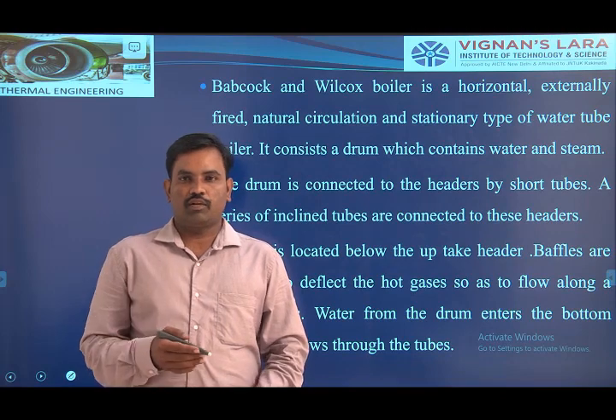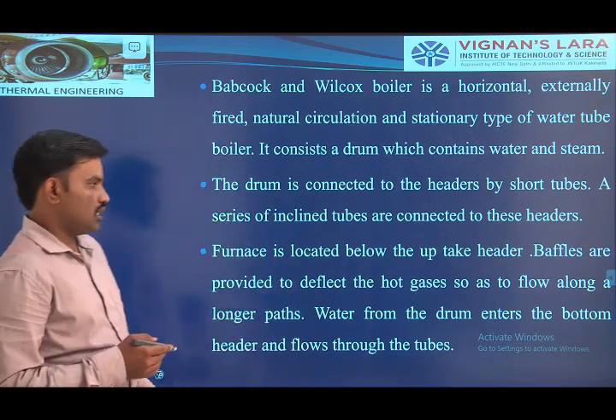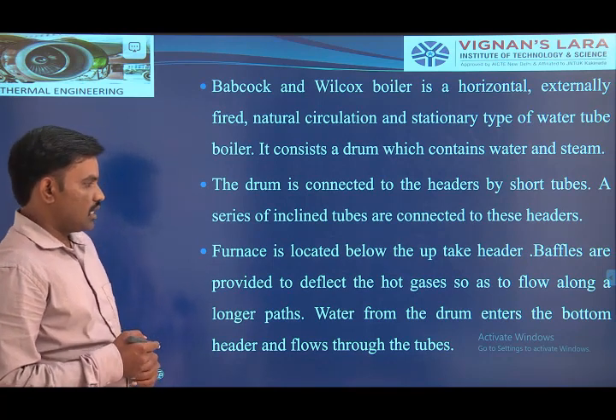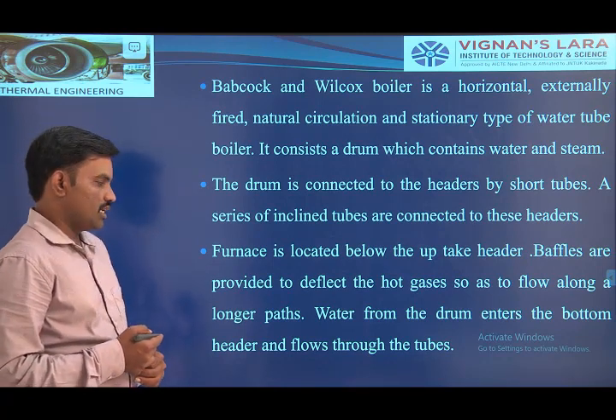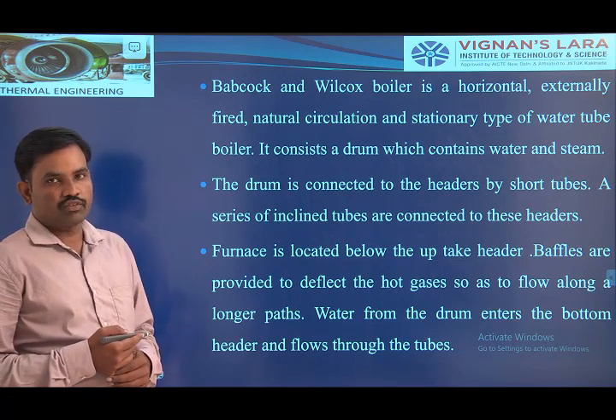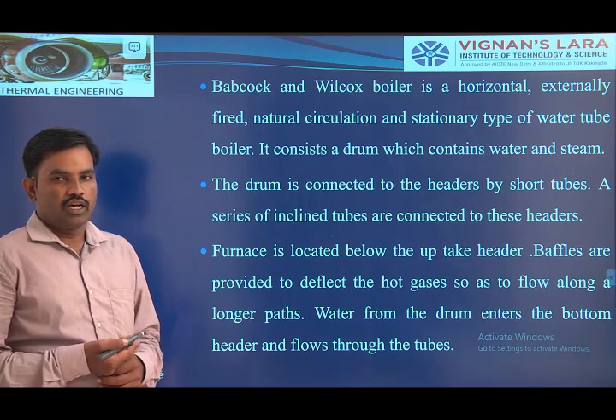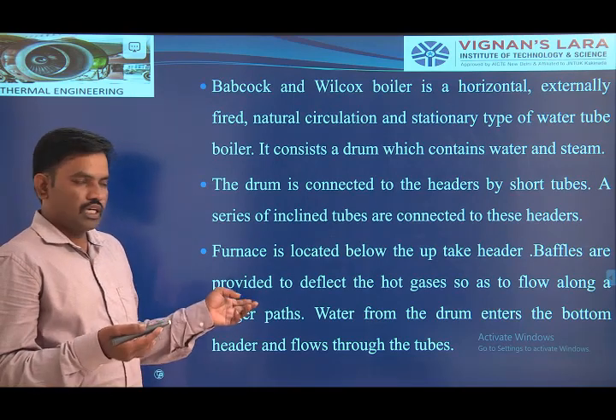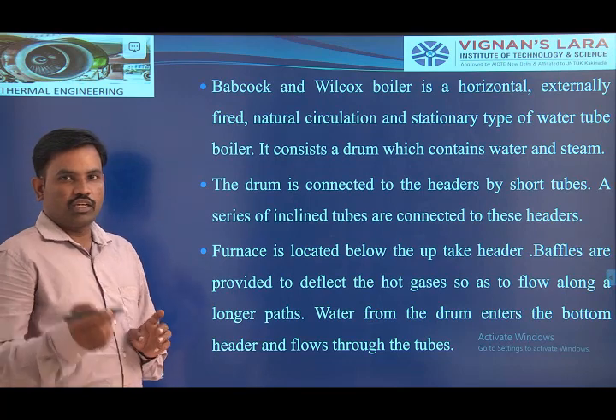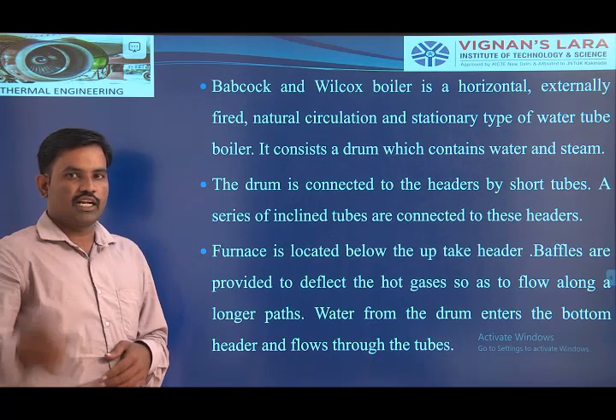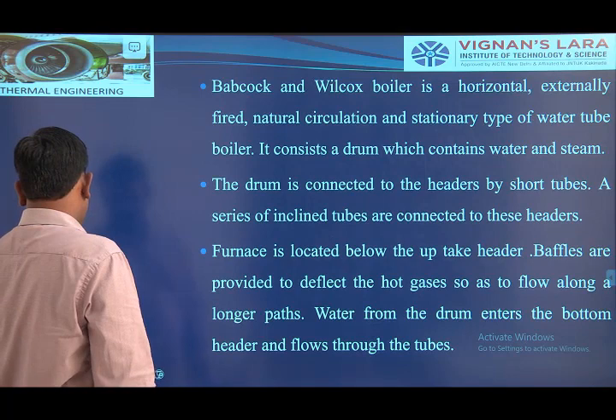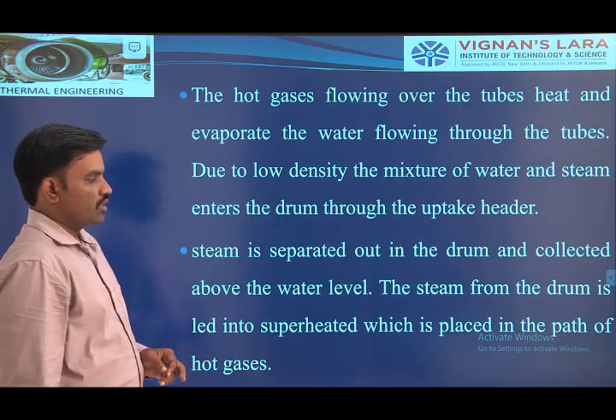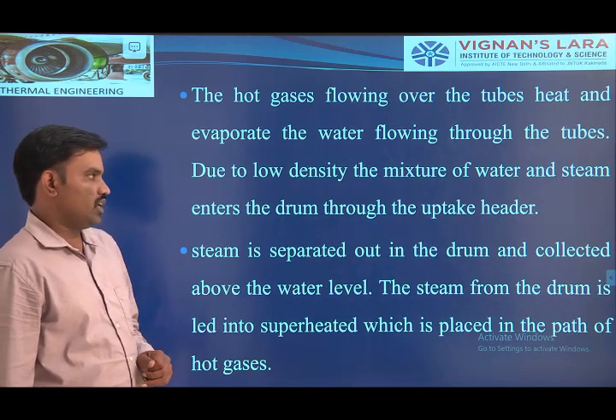By making obstructions with the help of baffles, we can increase the heat transfer rate from the hot flowing gases to the feed water. Water from the drum enters into the bottom header and flows through the tubes. Hot flowing gases flow over the tubes, water is converting into steam. After utilizing the gaseous energy, the gases escape into the outside atmosphere through the chimney. In that manner we are generating steam in case of the Babcock and Wilcox boiler.